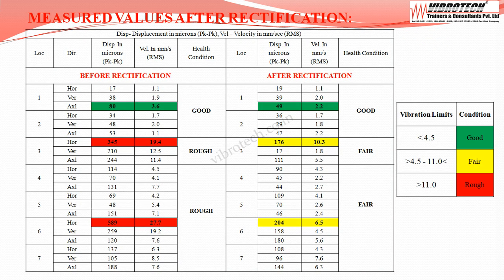After the rectification work, vibration levels decreased. The vibration values are maximum at motor non-drive end axial: velocity up to 2.2 mm/s rms with displacement of 49 microns peak to peak. At pulley free end bearing horizontal: velocity up to 10.3 mm/s rms and displacement of 176 microns peak to peak. At low pressure cylinder bearing horizontal: velocity up to 6.5 mm/s rms and displacement of 204 microns peak to peak.